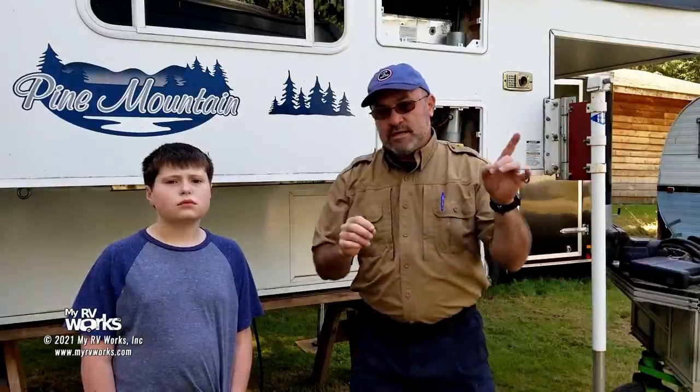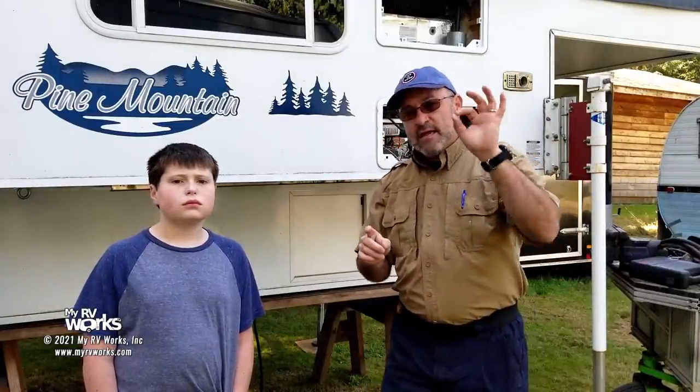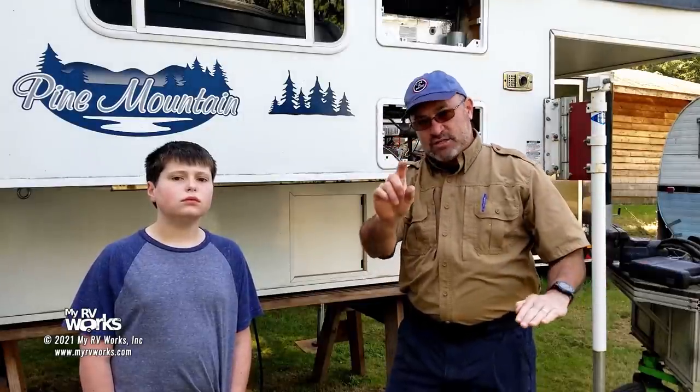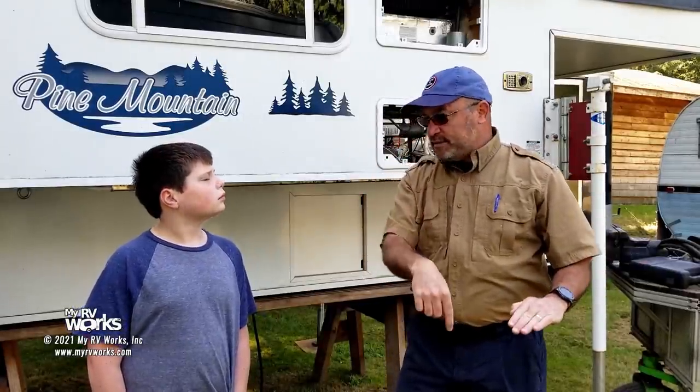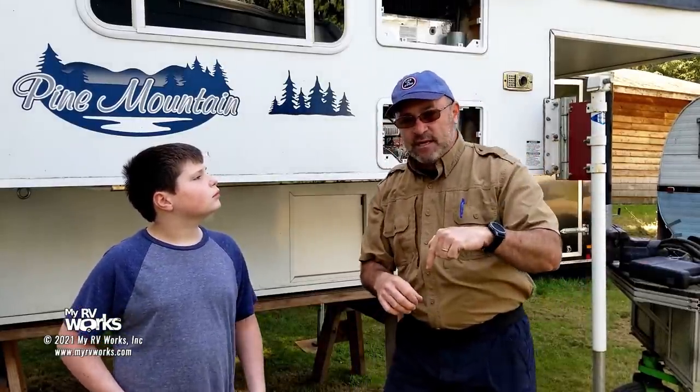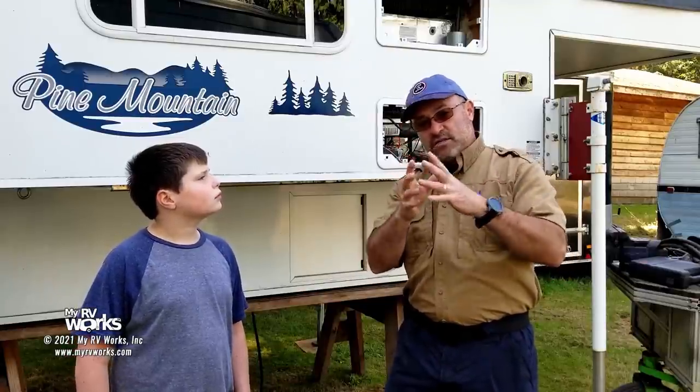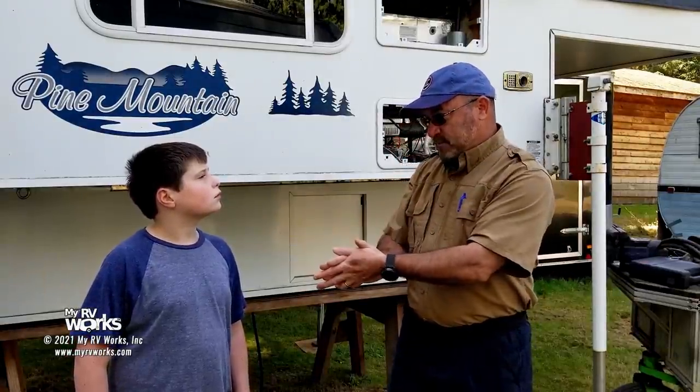And so we talked a minute ago about that ethyl mercaptan they add. The ethyl mercaptan that you might smell is below the point of combustion. Okay, it's down in the ones. So they'll put ethyl mercaptan in. So if you smell the ethyl mercaptan, that's below the 2.15% combustion threshold. Make sense?